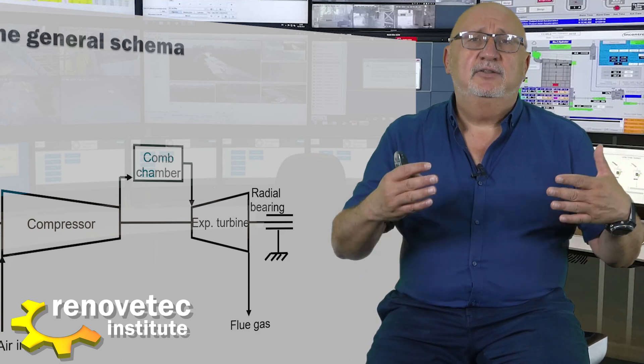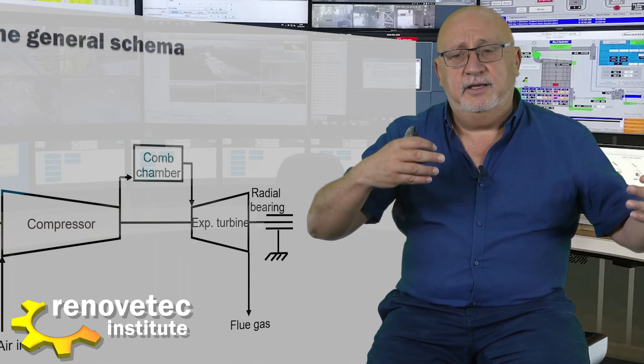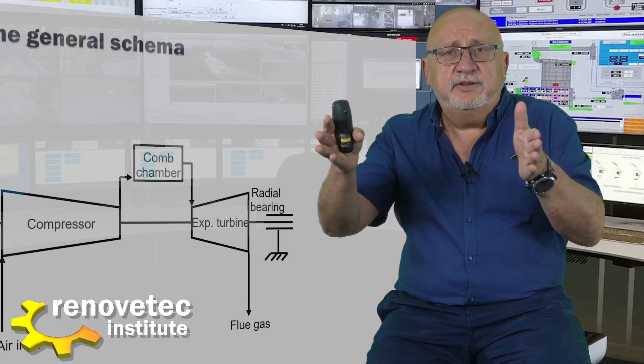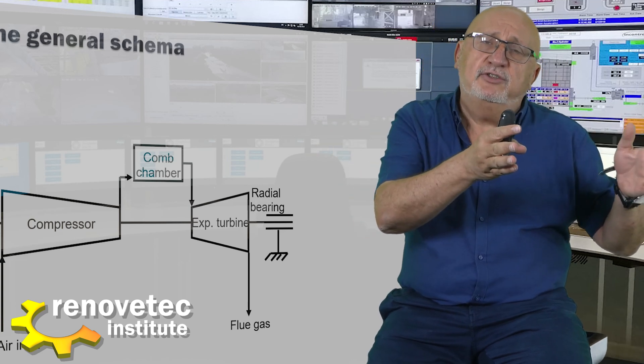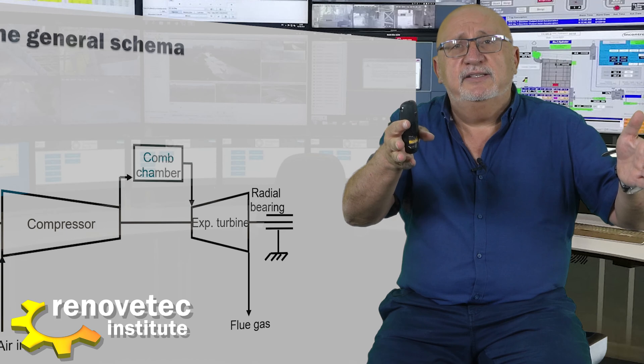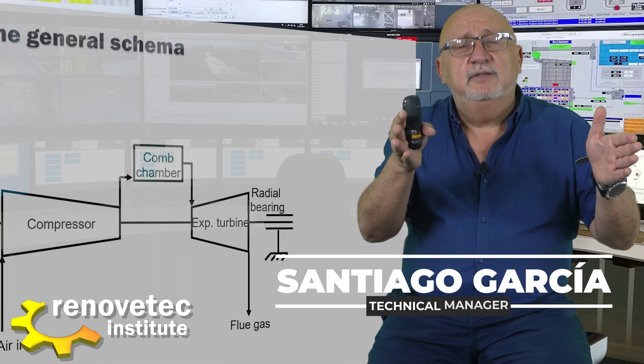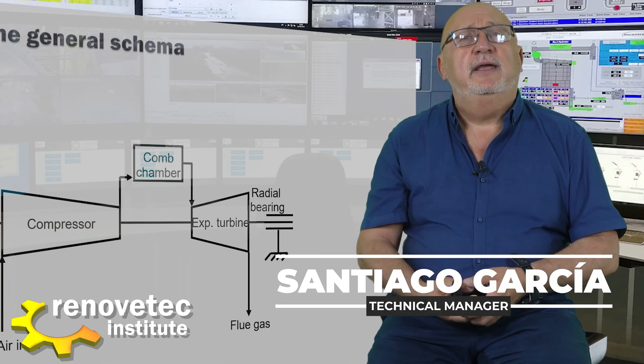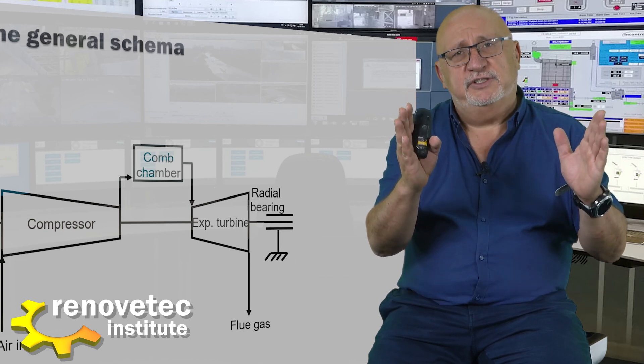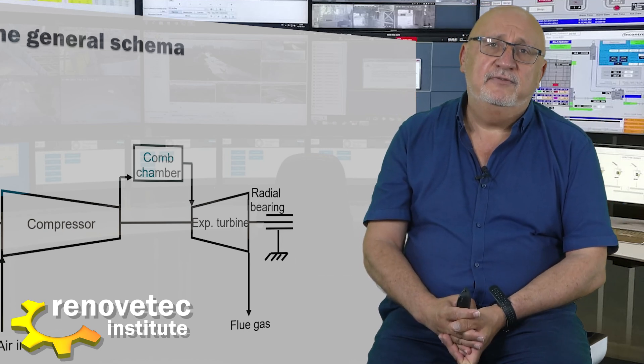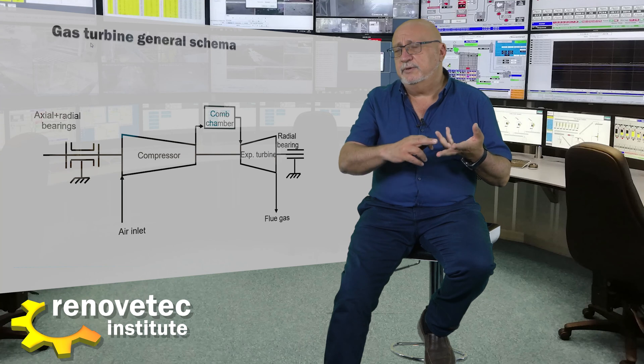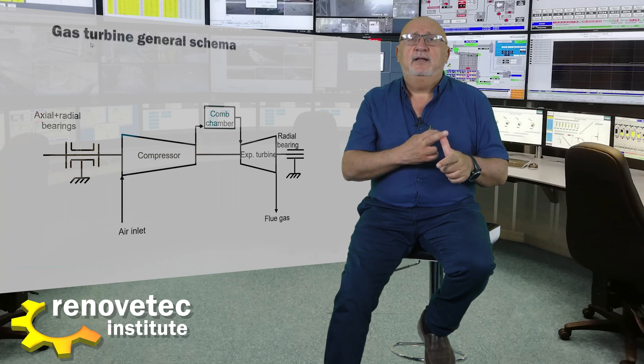The shaft also supports axial forces that try to move it in one direction or another, depending on whether the turbine is starting, running, or stopping. To avoid this axial movement, it is necessary to install another element to fix the position of the shaft — this is the axial bearing or thrust bearing. So for the moment we have: compressor, combustion chamber, expansion turbine, axial bearing, and radial bearing.